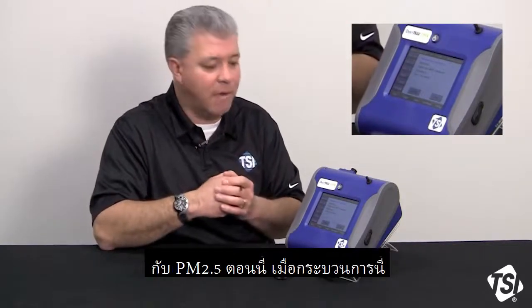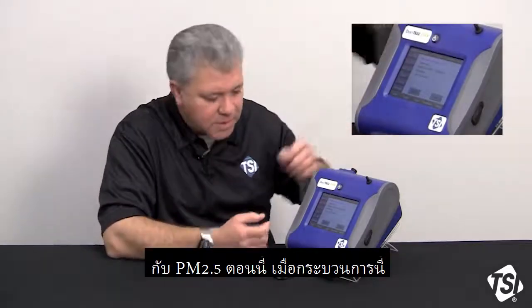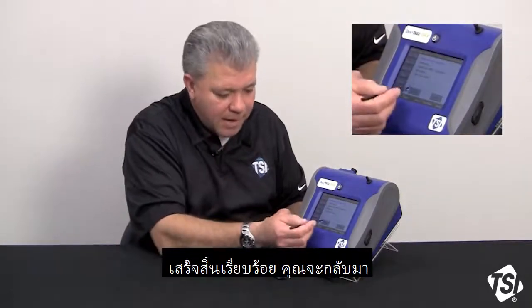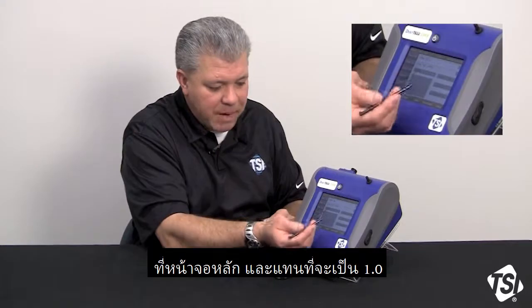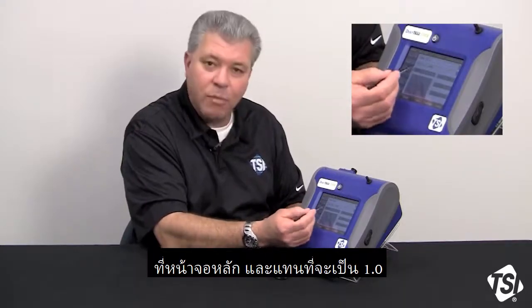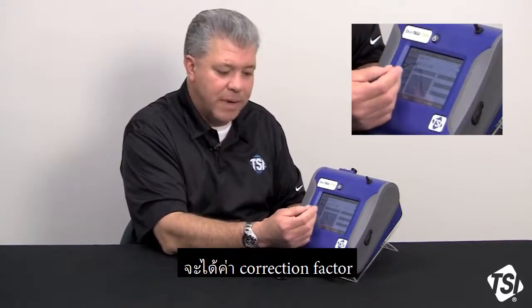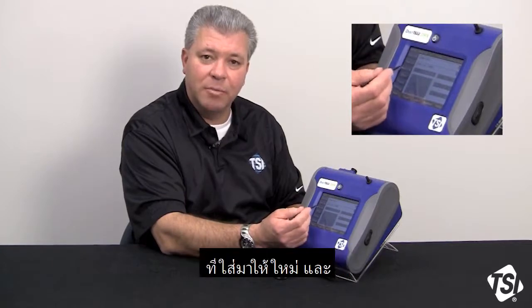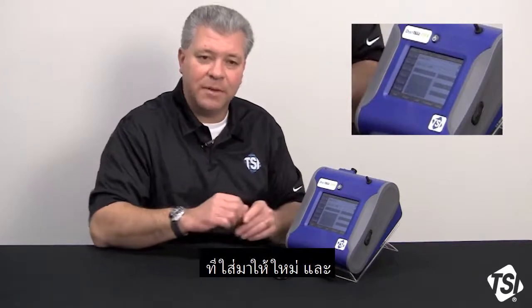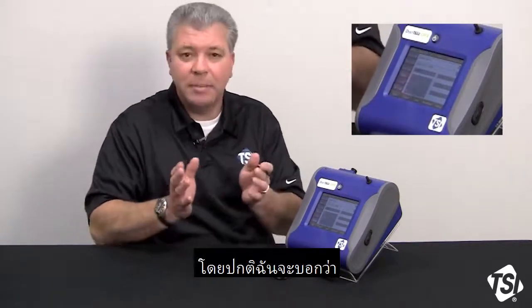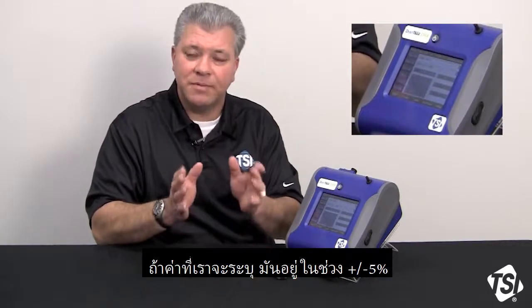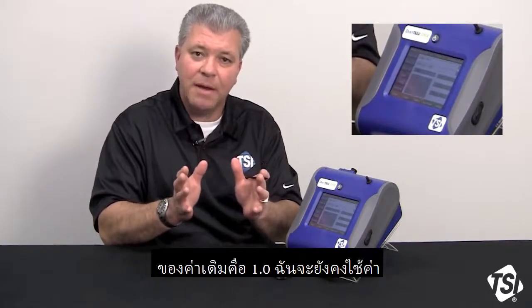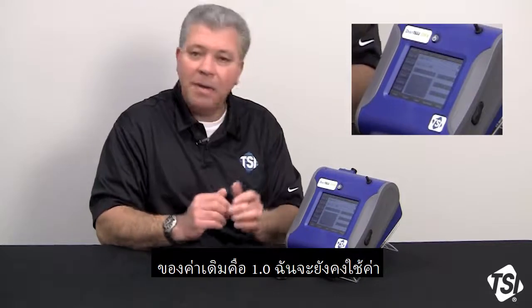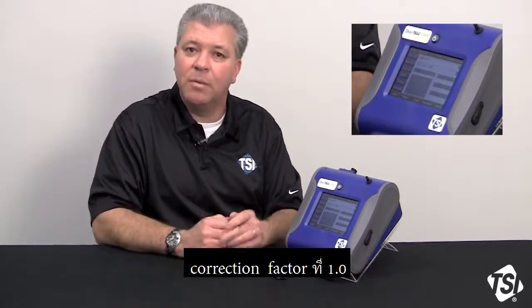Now, when this process is done, okay, you're going to come back to this main screen, and instead of 1.0, there's going to be a correction factor put in there. And that correction factor, I typically tell people if it's plus or minus 5% from 1.0, I would just leave the correction factor at 1.0.